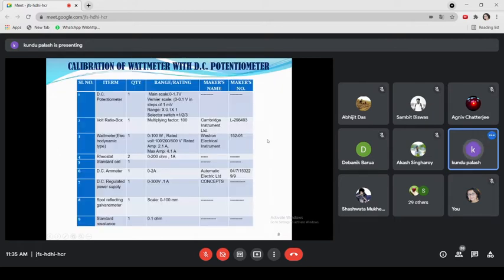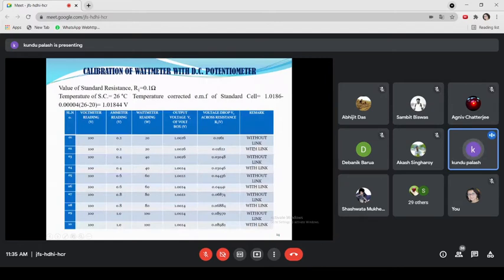So the current coil current will vary with and without the link. That's why in the sample observation readings, you will get different values without link and with link, which differ very, very slightly. With the link, the current of the current coil will increase to some extent, so the voltage across the current coil is different, though the difference is not 0.0. The phantom loading circuit is a without-link circuit, but in actual use of the wattmeter, this is the condition after placing the link. So this value is taken to be more practical, because the purpose of calibration of the wattmeter is to find the error of the wattmeter scale, and the wattmeter should be used in the with-link condition.